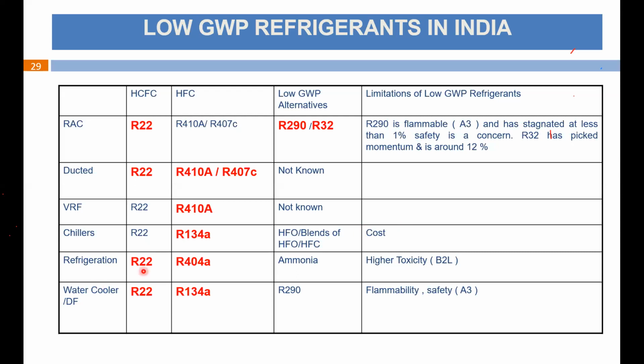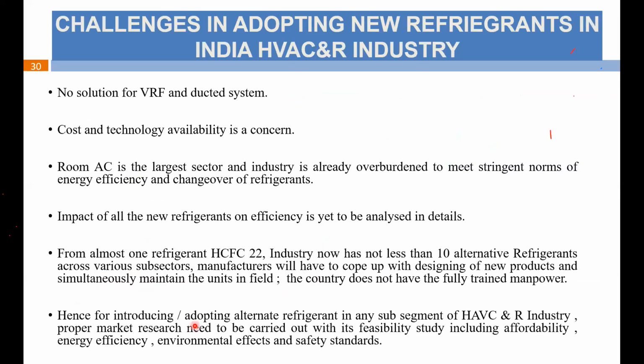For refrigeration, R22 and R404A are used, and the low GWP option is ammonia, but ammonia again has higher toxicity. For water coolers, we are still using R22 and R134A. The low GWP option is R290. So if I consider the challenges for the Indian HVAC industry in developing new refrigerants, till now no alternate refrigerant has been developed for VRF and ducted systems.